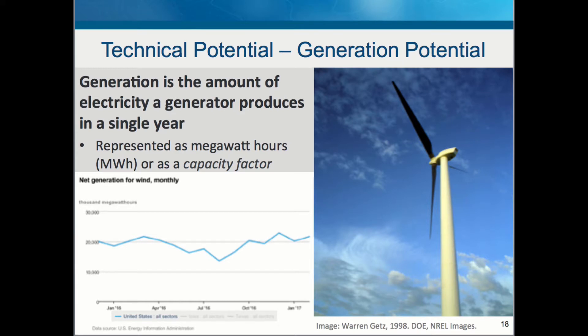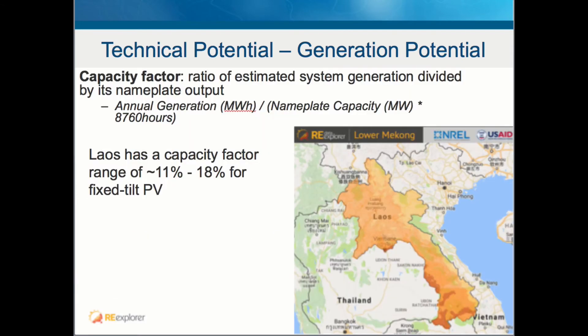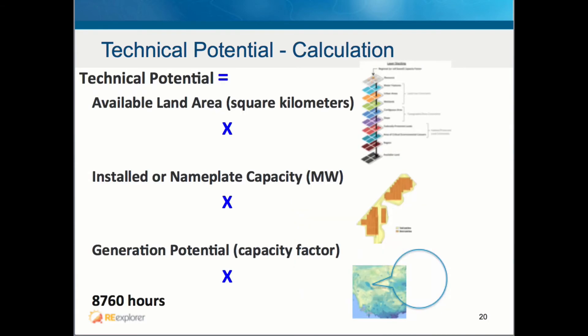Now that we have the nameplate capacity for our land area, we need to calculate the likely generation of our land area for a single year. Generation is represented as megawatt hours or as a capacity factor. A capacity factor is the ratio of estimated system generation divided by its nameplate output. Laos, for example, has capacity factors that range between 11% and 18% for fixed-tilt photovoltaics. We now have all the necessary inputs — available land area, nameplate capacity, and capacity factor — which are multiplied by the number of hours in a year, 8,760, to generate the potential resource available given technical constraints.